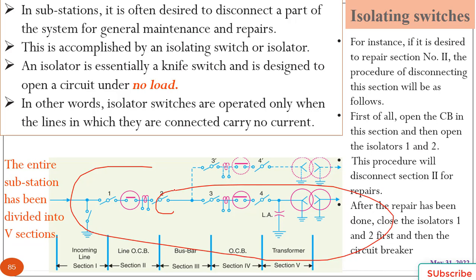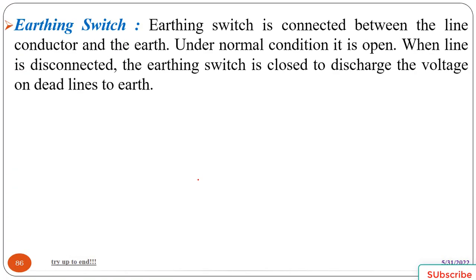This is a single line diagram. For instance, if it is desired to repair section 2, the procedure of disconnecting the section is as follows. First of all, open the circuit breaker in this section, and then open the isolators, this one and this one. This procedure will disconnect section 2 for repair. After the repair has been done, close isolators 1 and 2 first, and then close the circuit breaker to continue the supply.